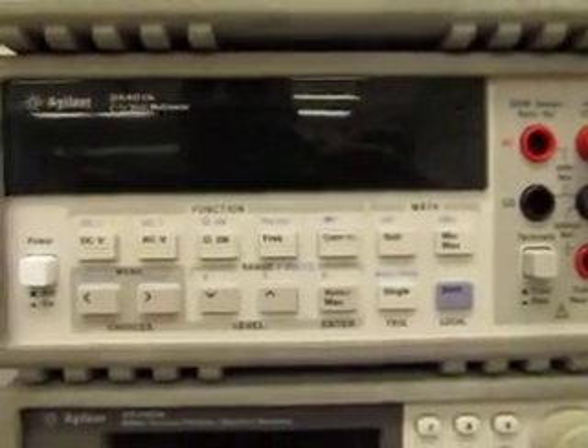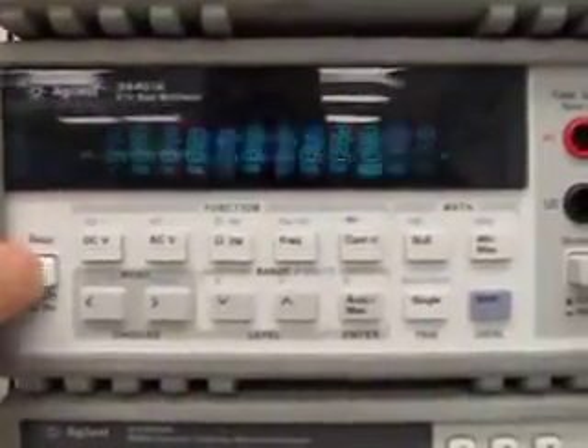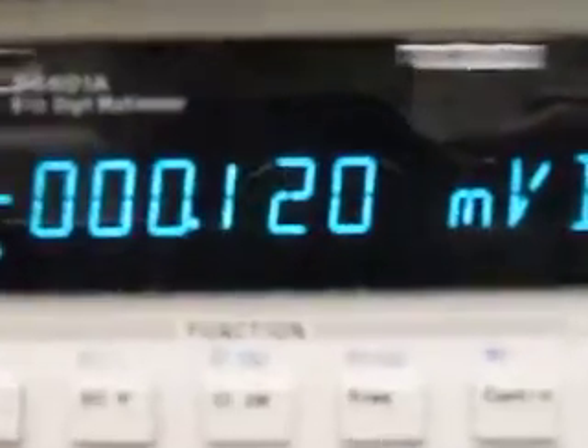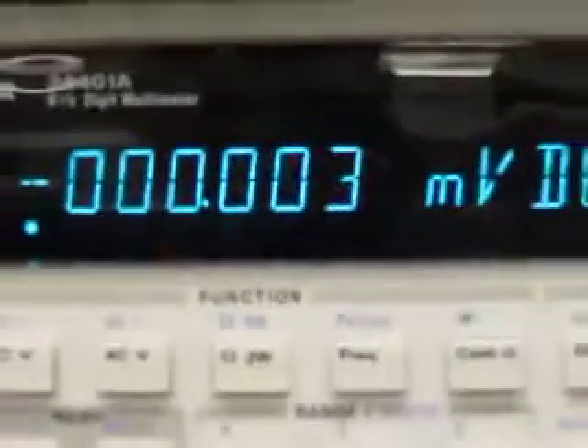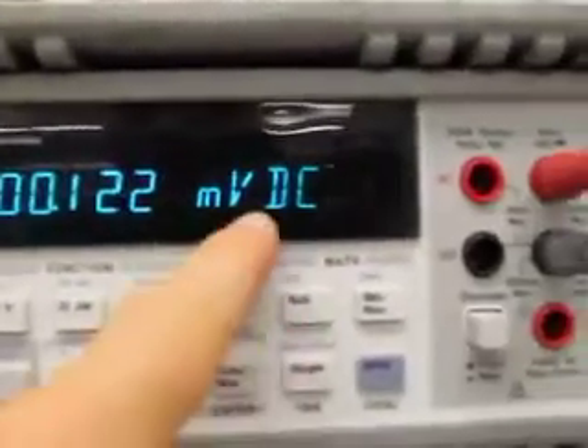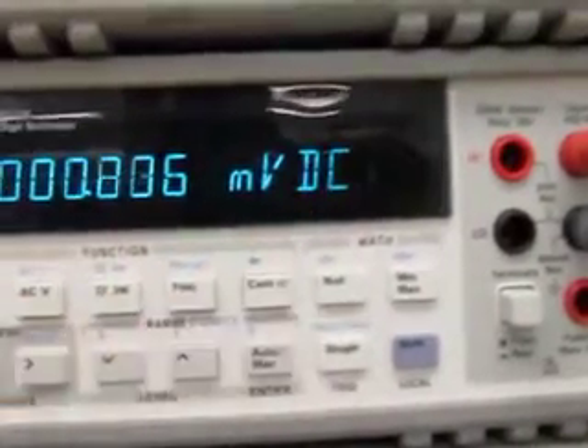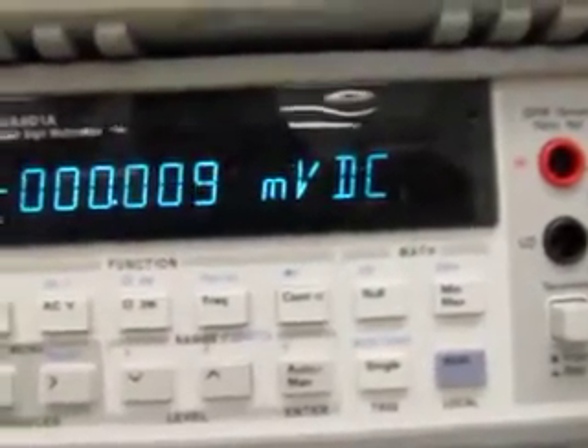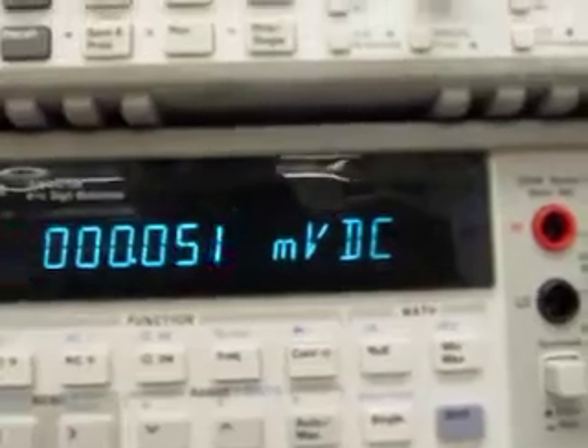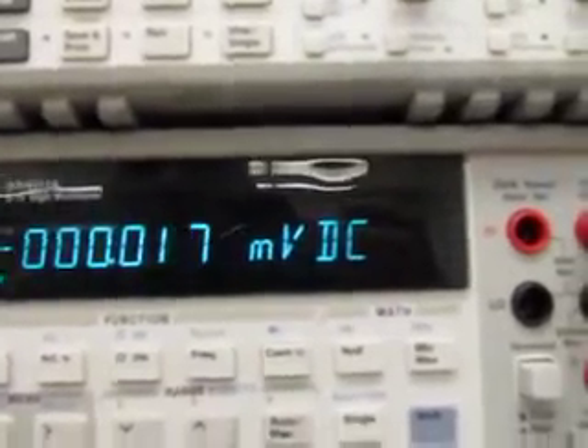Okay, this is a demonstration on how to measure DC voltage in an electric circuit using a 6.5 digit multimeter, which you see right in front of you. The first thing you want to do is press the power button, and you'll notice as soon as it turns on, it's set up to measure DC voltage. You see there's DC volts right here. Right now the voltage is jumping around, and that's because we're just measuring ambient voltage in the atmosphere.